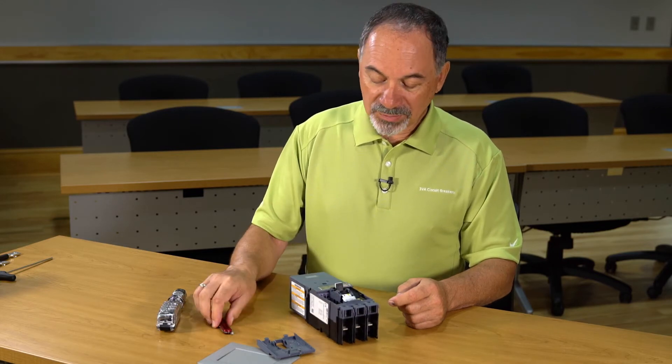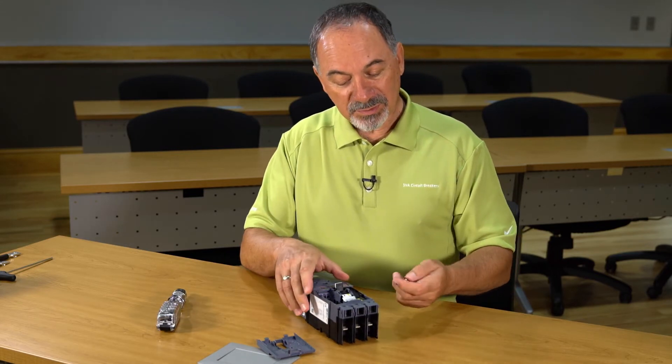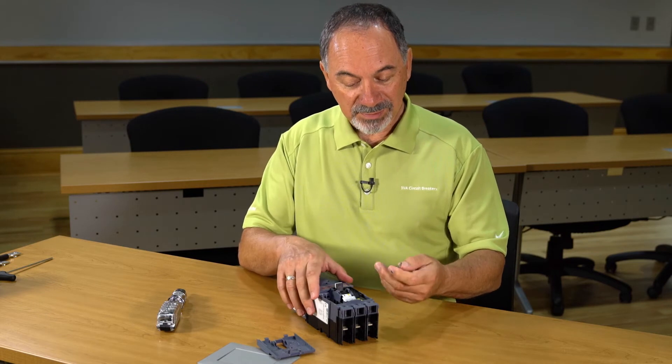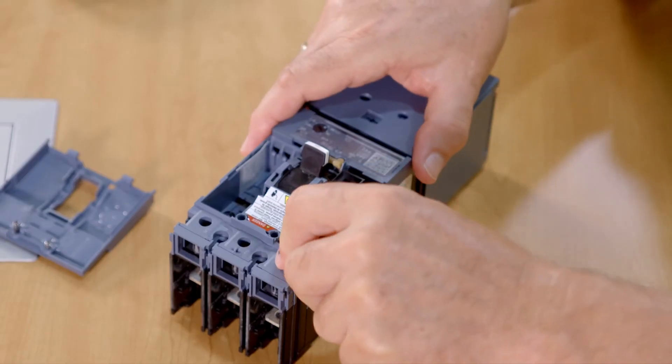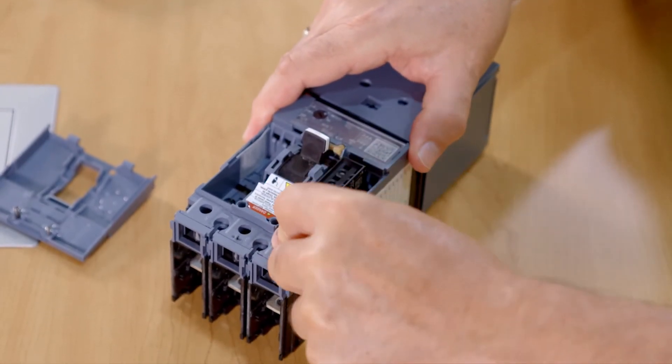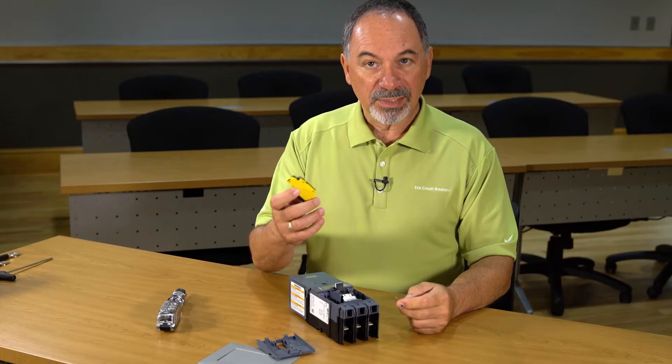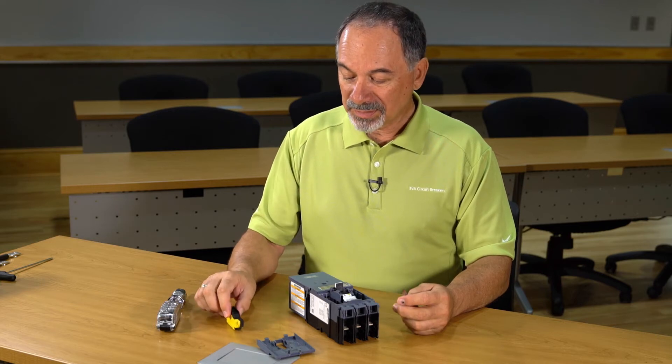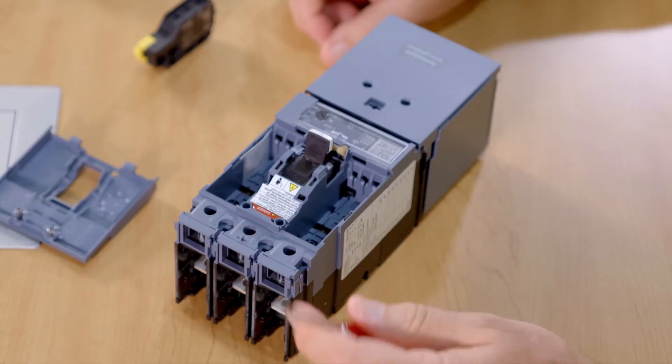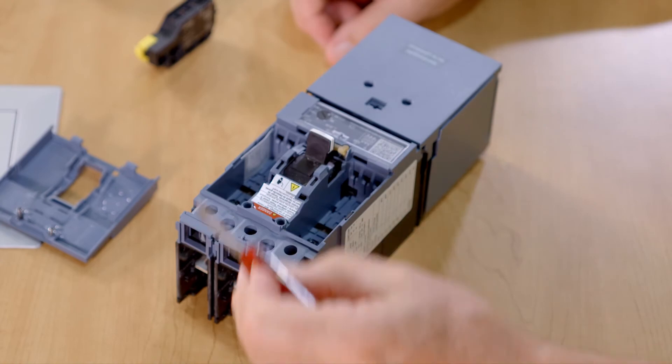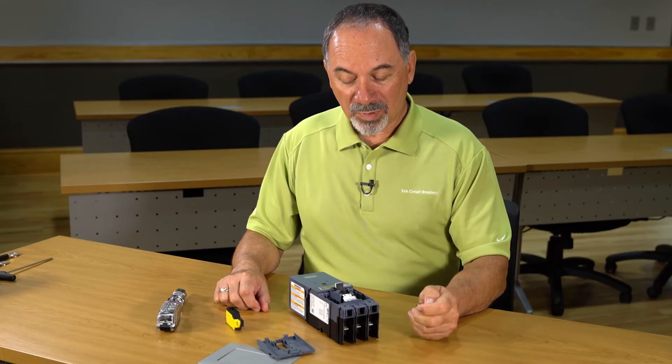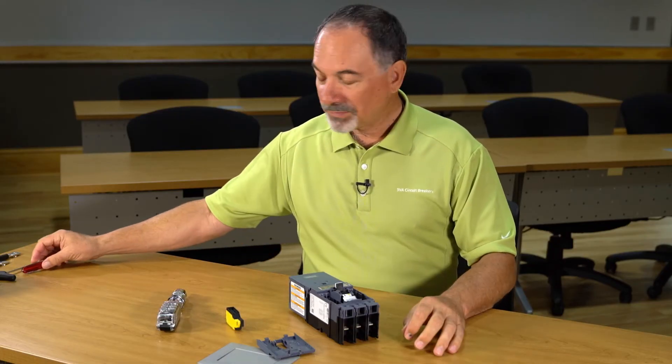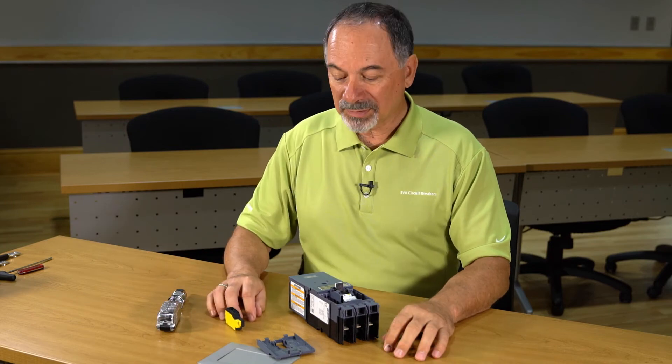To remove that accessory, in the event that you install it incorrectly, I usually use a blunt knife or a screwdriver. I can grab a hold of that accessory and remove it and we've installed and removed an internal accessory. These internal accessories, we can put up to six accessories in one 125 amp 3BA circuit breaker as required.